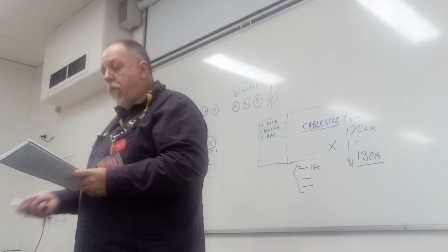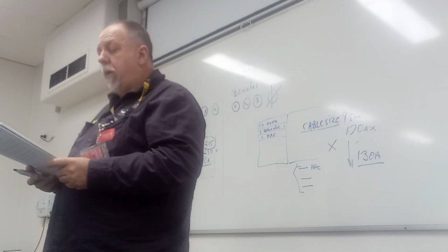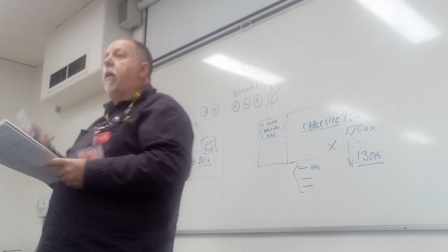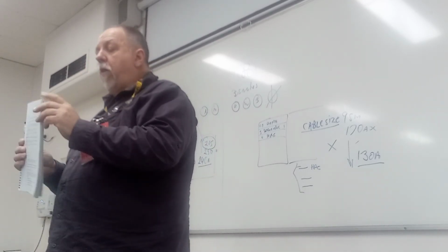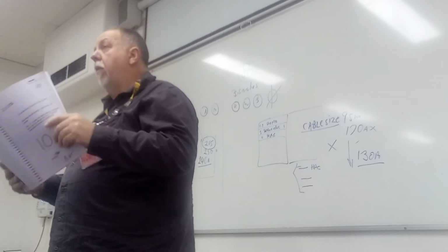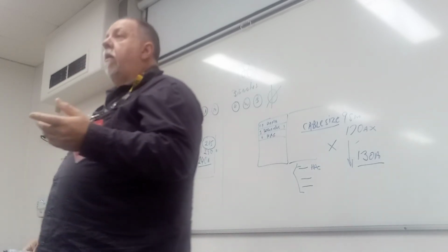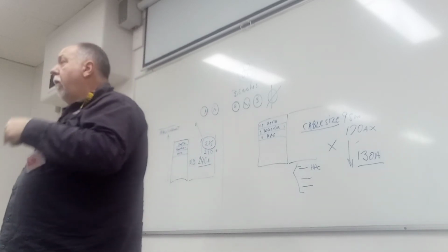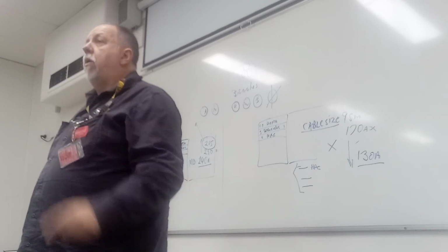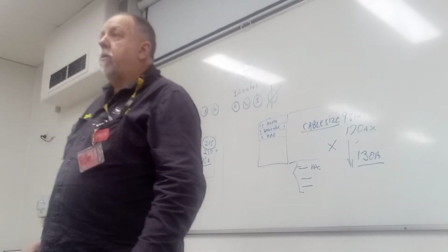If it has a resistivity of 1.5 or 1, then we have to apply derating. Notice some of these ones in here are a 1 or could be a 1.04 and all that stuff. That's where it goes from, as I said, being below 1, it can become a positive part, all right? Those 5 tables I would mark because those ones do not have any reference at all from tables 3.1 to 3.4. All right, you need to know where they are. Okay, so if the depth of laying is 0.7, table 3.1 to 3.4 will not tell you where that depth of laying table is. You need to know where it is. So appendix B in the back, you can mark that and highlight those 5 tables so that you know they relate back to as deratings.